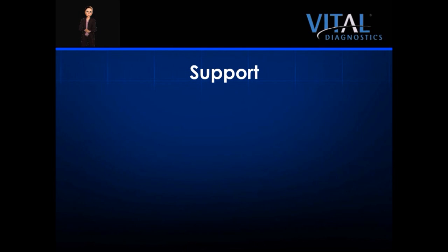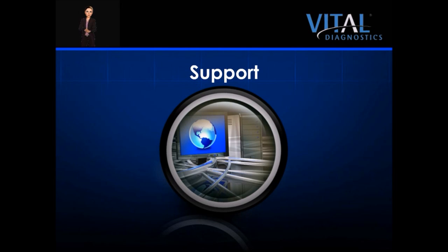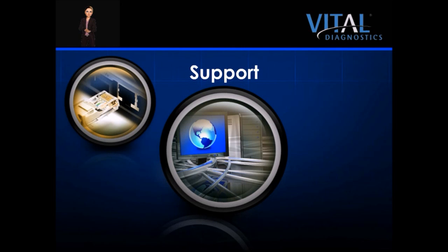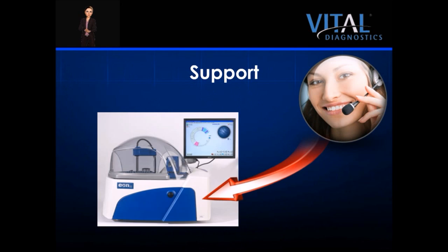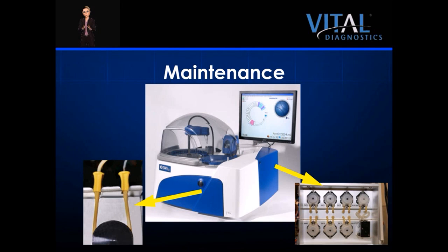Vital Diagnostics, or your local distributor, has the ability to dial in remotely to your instrument to assist with troubleshooting by way of viewer software. This service is limited and restricted to successful access to a network. A representative can remotely access the behind-the-scenes service software, which records and logs all instrument activity for advanced troubleshooting. If service is covered by Vital Diagnostics, the system is virtually maintenance free. Tubing, pumps, and cuvette replacement are all done during preventative maintenance visits. Otherwise, replacing these products is simple and should take less than 30 minutes a month.